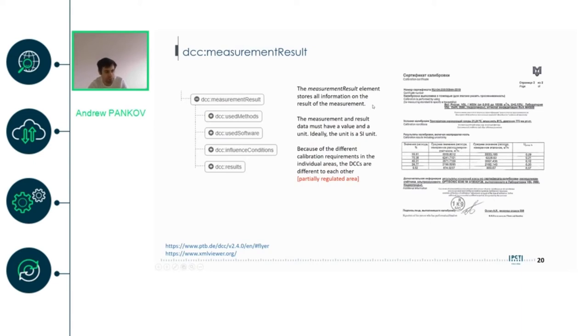The measurement and result data must have a value and a unit. Ideally the unit is an SI unit, because of the different calibration requirements in individual areas, the DCCs differ from each other. This part was a partially regulated area and consists of some sub-elements.